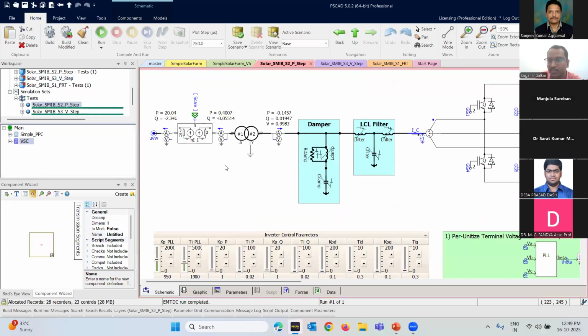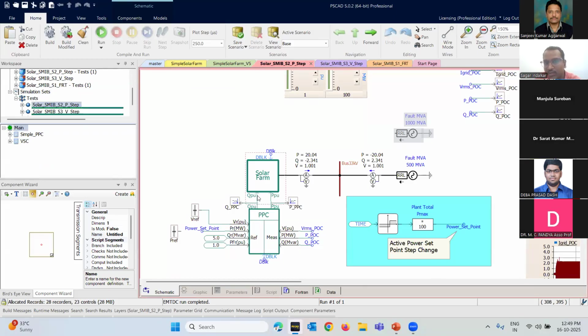Okay. So this is your converter. If you see these wires here, UP, PU, these are the references to the converter. And where are they coming from? They're coming from your PPC. So this block is your PPC. And on the left hand side, what you see are the references. So typically, PPC performs five functions: active power control, reactive power control, voltage control, frequency control, and power factor control. So this PPC performs only four controls. It doesn't have a frequency control function, the one which I have in front of me. So it requires four references: voltage reference, active power reference, reactive power reference, power factor reference.